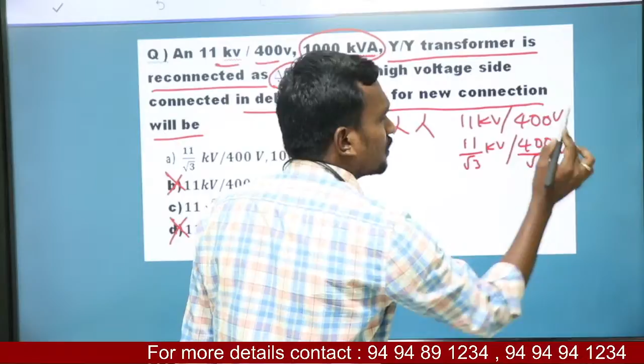For star-star, they gave the voltage rating as 11 kV upon 400 volts. Is this the line turns ratio - line voltage ratio or phase voltage ratio? This is the line voltage ratio, so we have to convert into phase voltages. The phase voltage for star equals line voltage by root 3, and for 400 also, it's 400 by root 3 volts. This is the phase voltage for star-star.